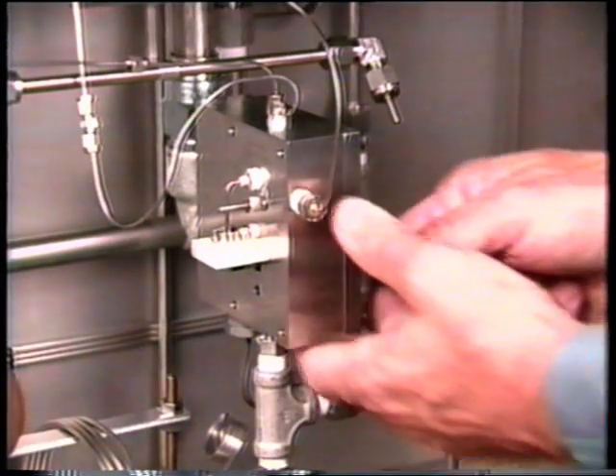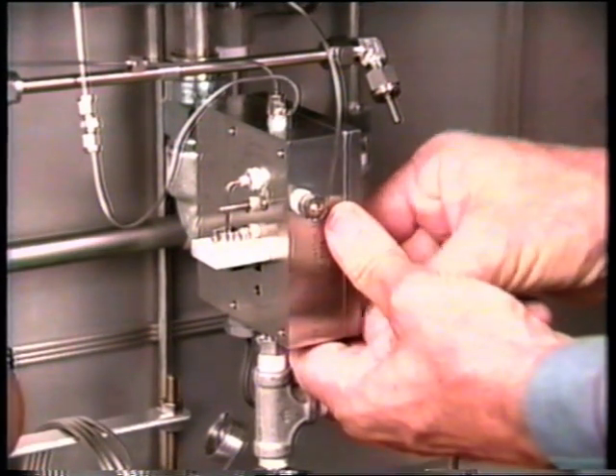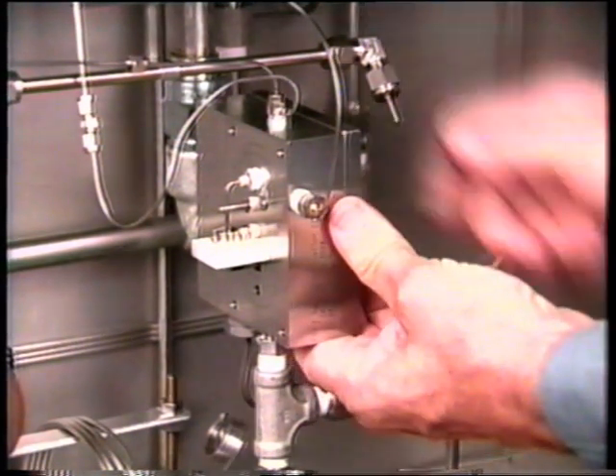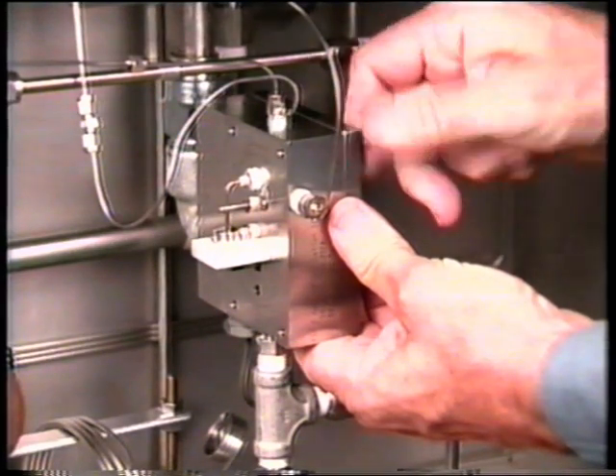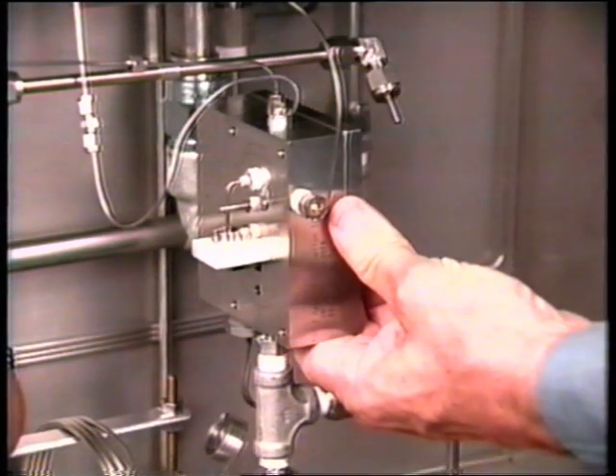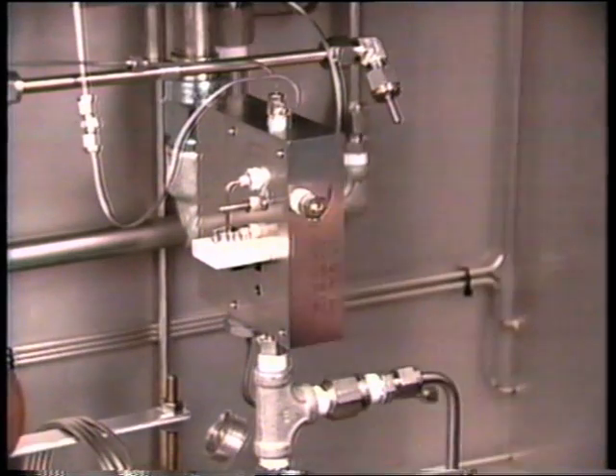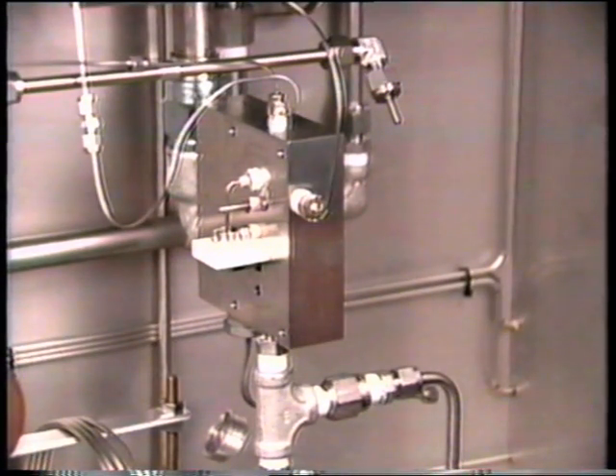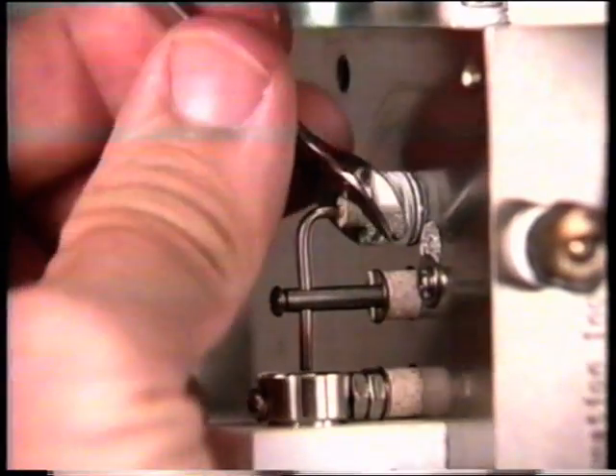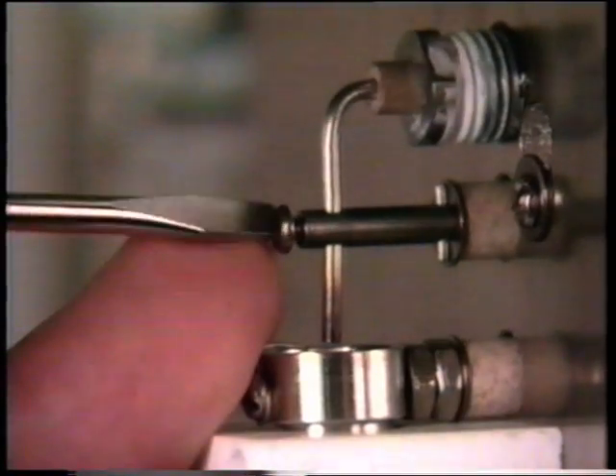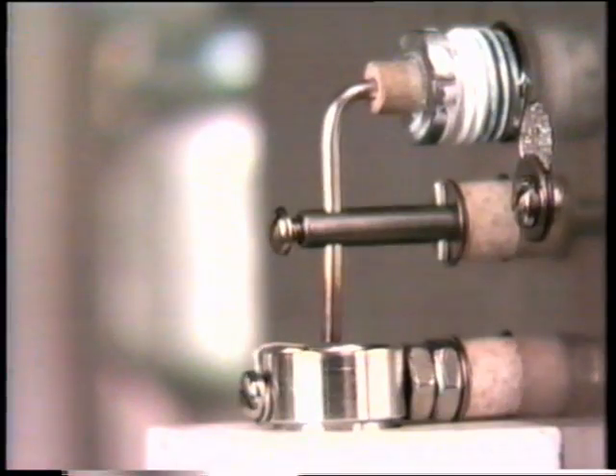One of the most frequently required procedures for the FID is replacement of the burner tip. This can be accomplished while the detector is still in the oven. To replace the burner tip while still installed, remove the sensor and terminal covers from the detector. Loosen the burner clamp. Loosen the screw in the end of the bias ignite electrode.